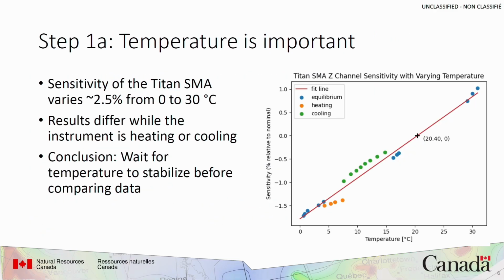So we did that over a couple of days in spring in Canada, where the temperature varied by 20 degrees or 30 degrees. And the accelerometer itself has, not surprisingly, a fairly strong temperature sensitivity. Furthermore, while the instrument is heating or cooling, the errors are larger, so that tells us that it's important to let the temperature stabilize before doing this test.